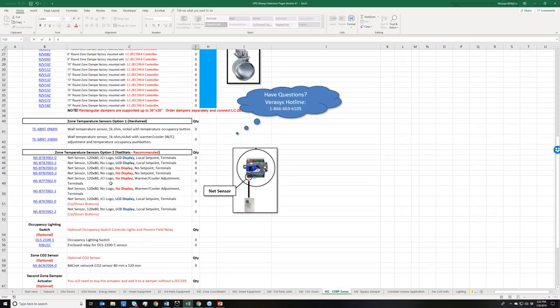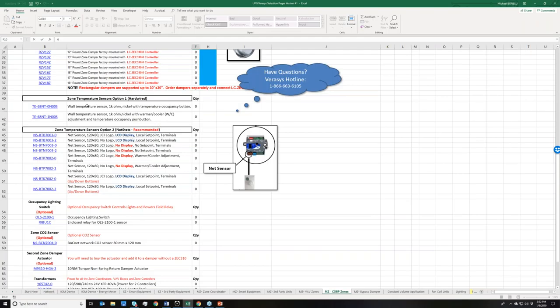And I have two options for zone temperature or space temperature. I can use either hardwired sensors connected to the controller, which will go physically on the inputs, or I could use the NS sensors. Now, because we have the VAV boxes using NS sensors, it just makes sense to be consistent throughout the job. I would want to do that. We do have instances where people want to do plate covers for hardwired sensors, so they're going to go that route instead of having the wall mount NS sensors. That's why we offer that feature.